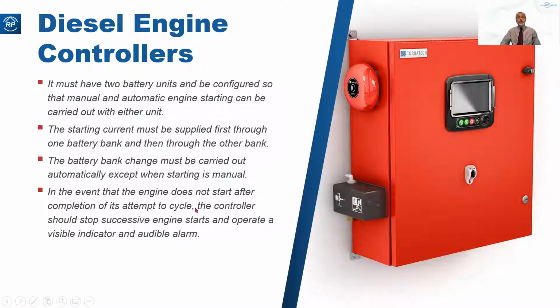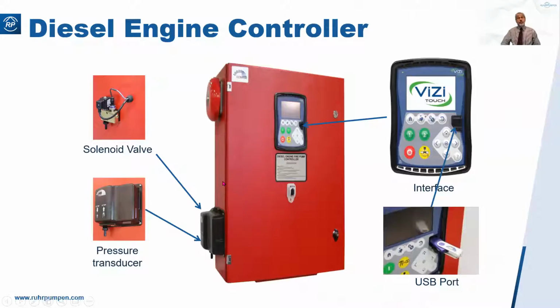Diesel engine controllers. These will control the logic for the start attempts, the 6 start attempts of 3 from each. And again, we have pressure transducer with a time delay. You'd probably want to make sure that the jockey pump had a chance to build up the pressure, and then the electric driven pump before you kick in the diesel driven pump. So again, solenoid valve to initiate the weekly test start.